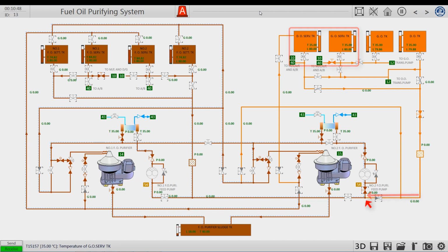Separators can also be used to separate the light oil in a service oil tank. Then it goes through the filter and the supply pump, goes to the heater. When the oil separator separates the light oil, no need to go through a heater. So the fuel enters the separator from the bypass line. This is the inlet line.